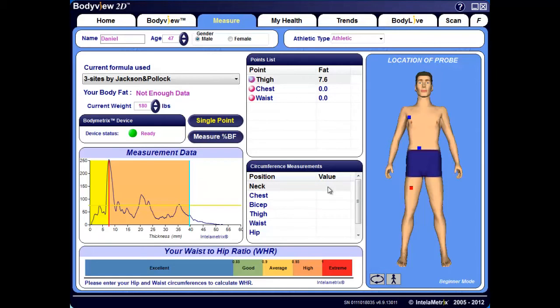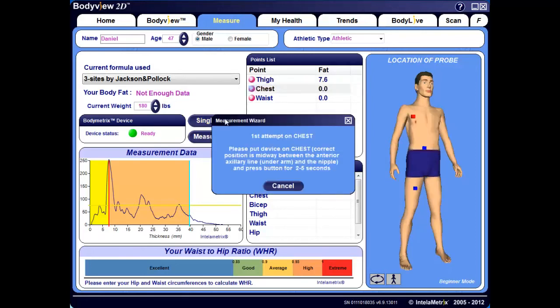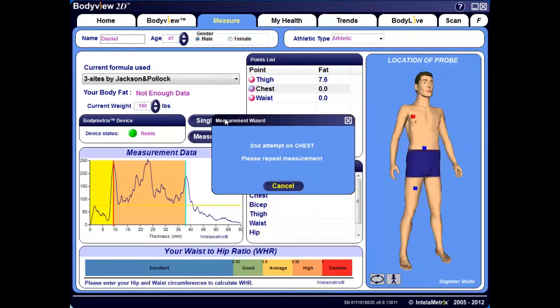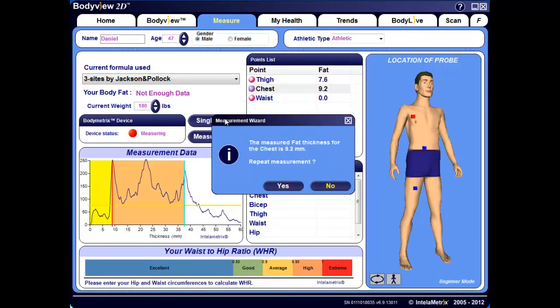There may be occasions where the software prompts you to take a third measurement, and that's just because the first two measurements disagreed by more than 10%. Next, click on the chest site point and then click the single point button. It's not necessary to wipe the device clean between measurements, but you may need to add a small amount of gel to ensure it slides easily on the skin. Spread the gel within the optimal area and, using the averaging technique, press the button and slide the BodyMetrix device diagonally back and forth, a quarter to a half inch on either side of the site point. Then repeat the measurement. The fat thickness is 9.2 millimeters, and the first large characteristic peak again lines up with the red vertical line, so select No from the dialog box to move on to the next point.